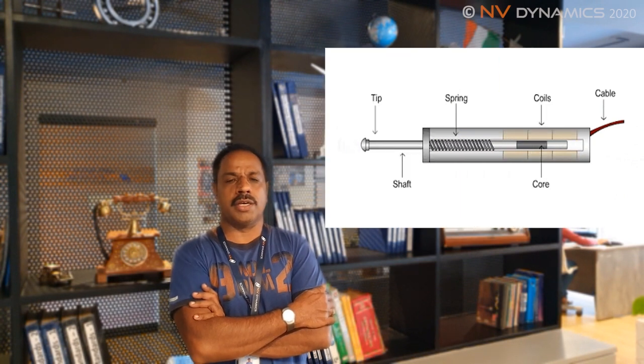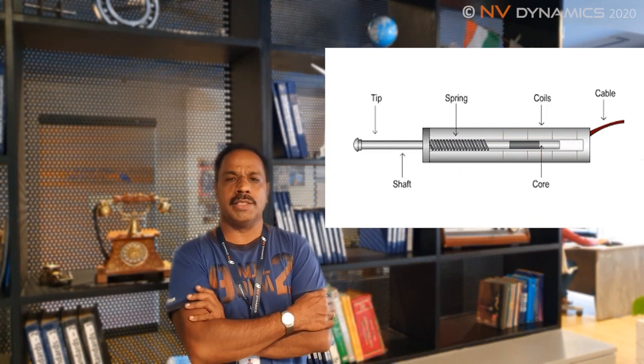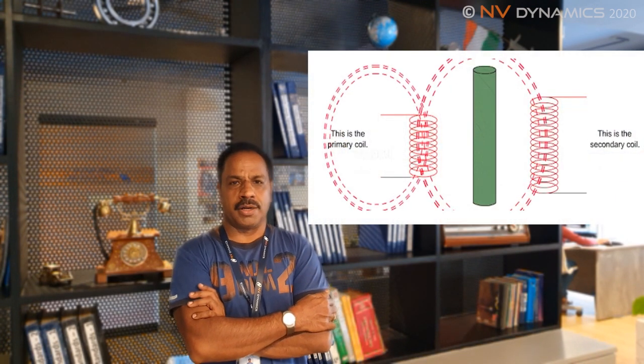In a way, a displacement transducer and a velocity transducer by construction could be compared — I am referring to a non-contact type. But essentially, in a velocity transducer, it uses mutual induction as the basic principle. There will be two electrical coils in the influence of which an armature moves. The armature is centered such that the net voltage or current output from these two coils will be null or zero when there is no motion.